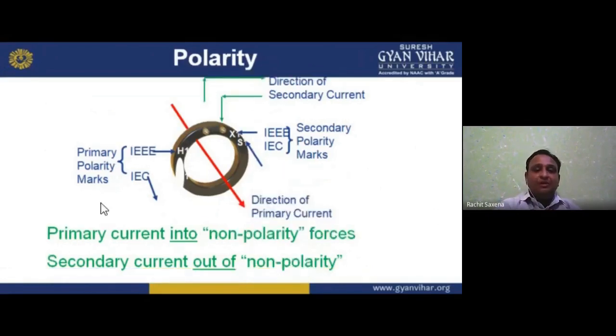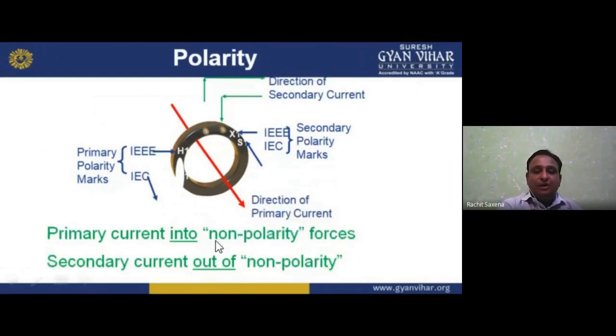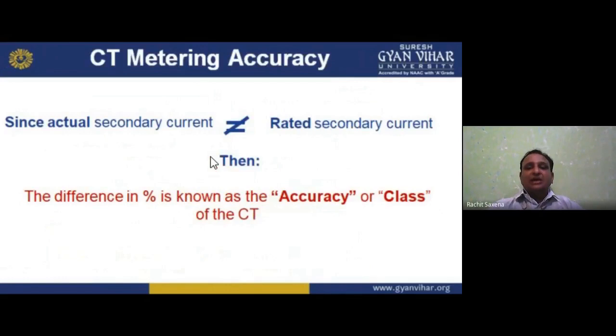Now again I am showing you here: primary current into the non-polarity, secondary current out of the non-polarity. See here, again the direction of the secondary current. We have the IEEE and IEC secondary polarity marks, and the primary polarity mark. Here is the direction of the primary current input, so the output is at the polarity of the secondary. So primary current into the non-polarity, and secondary current out of the non-polarity. Try to understand what this diagram wants to tell you, my student, and what I want to show you through it. And it is a ring structured CT. We have different types of CT, and that is the ring structure. Now, CT metering accuracy. Since the actual secondary current is not equal to the rated secondary current, the difference in percentage is known as the accuracy or class of the CT.